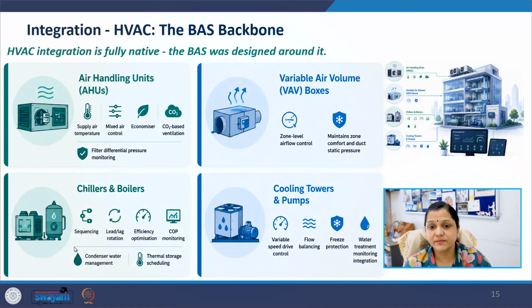The HVAC integration forms the backbone of most BAS installations. The BAS continuously manages air handling units, VAV boxes, chillers, boilers, pumps, and cooling towers. For AHUs, the BAS controls supply air temperature, mixed air conditions, economizer operations, and ventilation rates.